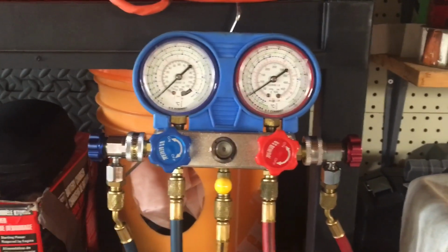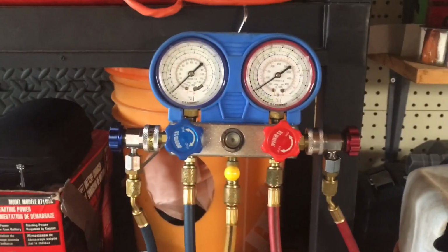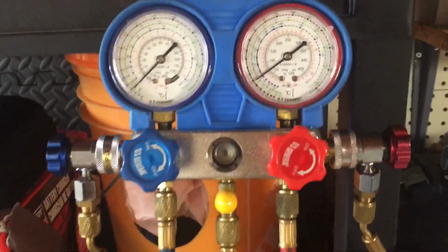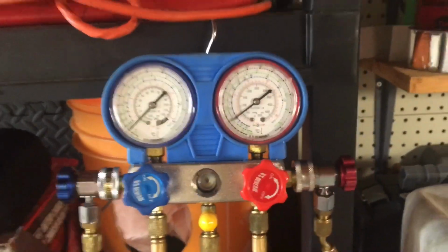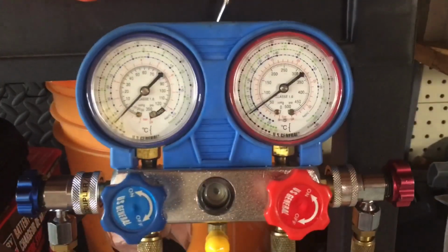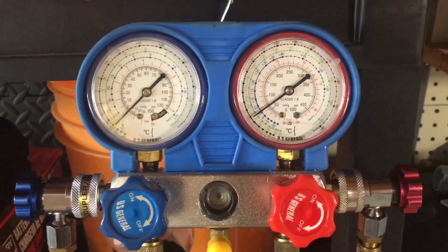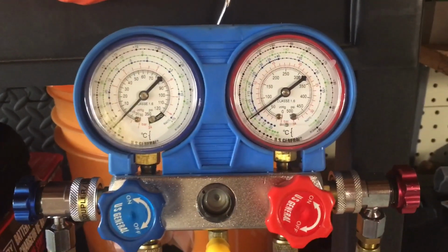So I want to try a couple more leak check techniques. Nothing really new, I'm going to put the nitrogen bottle on it, get the nitrogen regulator hooked up, and pump the system up to, I don't know, a bit higher than normal, maybe 150 pounds or so, and see if we can get it to leak. I haven't been able to get it to leak in the past.